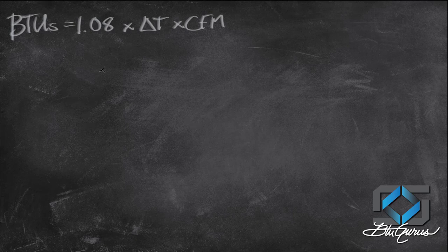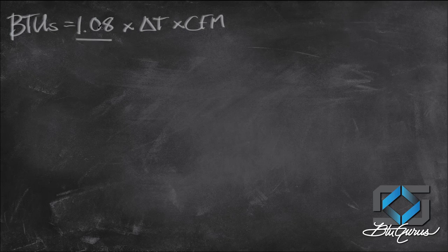Before I go into the actual equation, I want to make a comment about what 1.08 is. It actually has to do with the specific weight of air, and this will be affected by elevation change. So 1.08 is sea level.